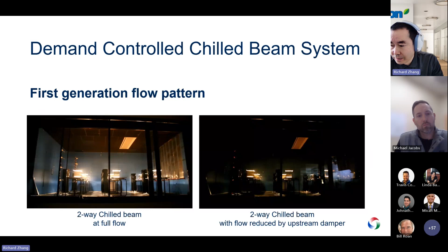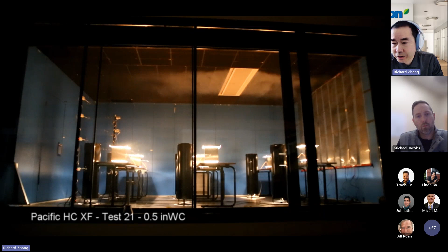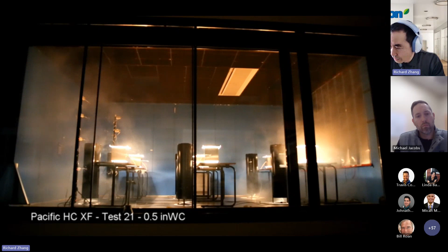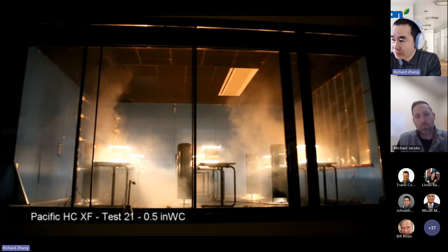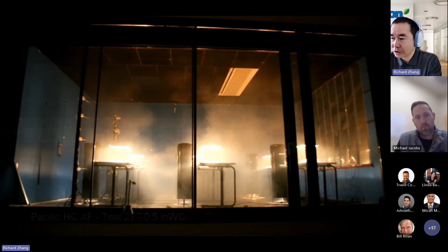So I'm going to show you two interesting video clips from our testing lab. The first one shows the two-way chill beam designed properly. You can see the air coming out, sticking onto the ceiling because of the Coanda effect, and then you make sure you flush the wall. So you're taking care of all those sensible loads. At the same time, did you see the air coming back to the chill beam? That is because of induction. So that is a properly designed chill beam system, mixing the air very properly and distributing the proper temperature in the room.